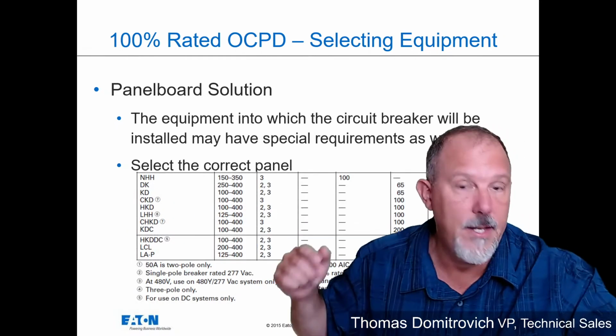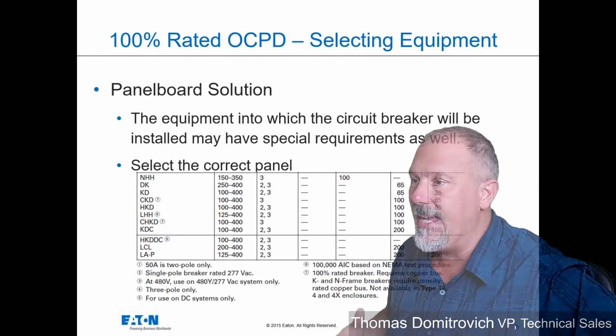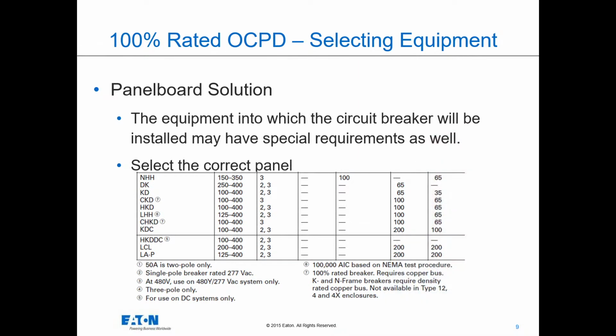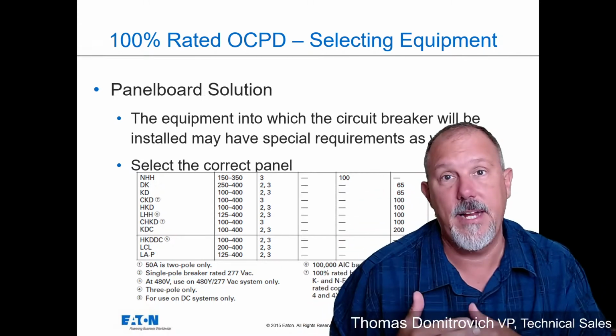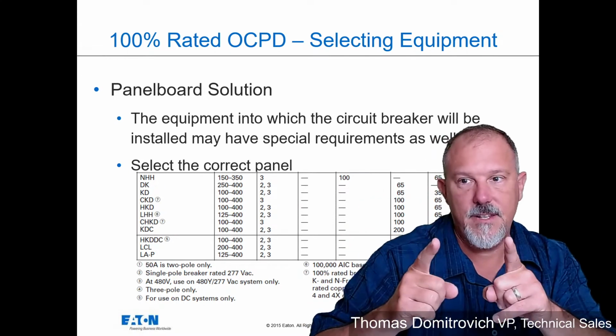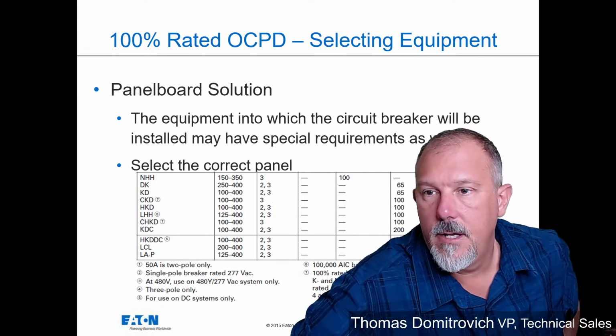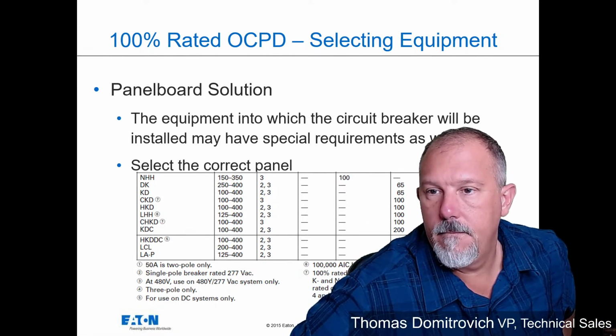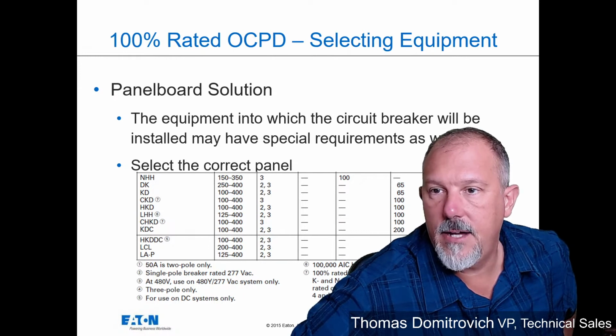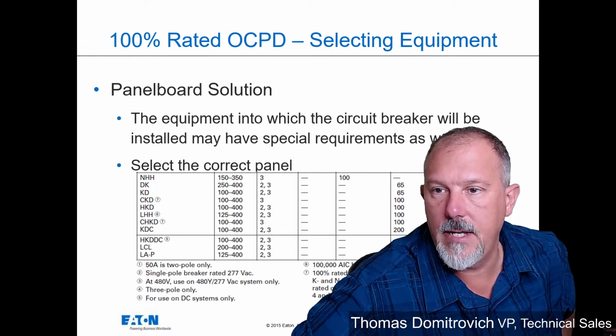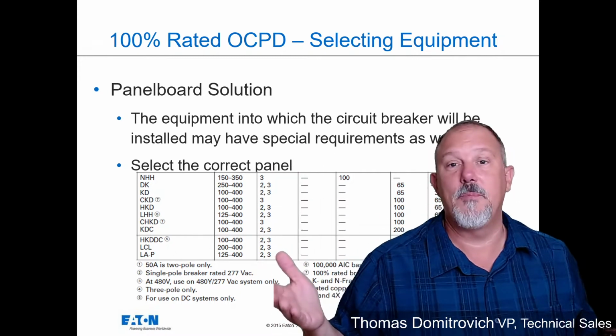Take a look at this one right behind me. It says 100% rated breaker requires copper bus. K and N frame breakers require density rated copper bus, not available in type 12, 4, and 4X enclosures. So this is telling me that I need density rated copper bus. That's a little different. I think the caution is if there are other breakers in the assembly rated 80%, well, these are all rated 80%.